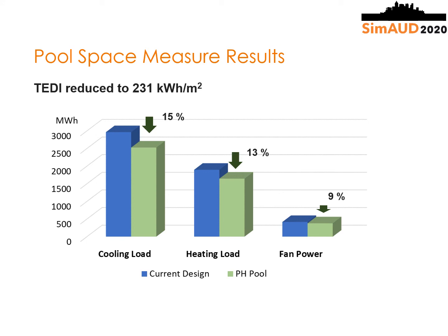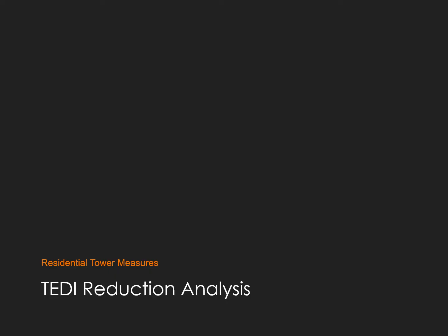So here are the results from our study. From implementing those 3 measures, we were able to lower the cooling load, the heating load, and also the fan power. And finally, the TEDI was reduced to 231. So still not meeting the 201 target, but getting closer.